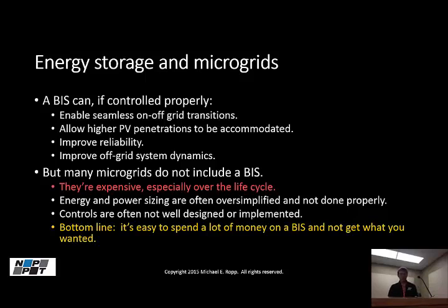Battery inverter systems, as we all know, are extremely expensive, particularly over the life cycle, because you'll have to replace the batteries probably a couple of times during the life cycle of the system. That gets very expensive. But one of the things that we find is that the controls design and the system sizing are often oversimplified. And the problem then is the nightmare scenario. You can end up spending a lot of money and get a system that does not do what you intended it to do. So again, you want to make sure that the design process is done correctly. And modeling is a good way to get a start on that as well.